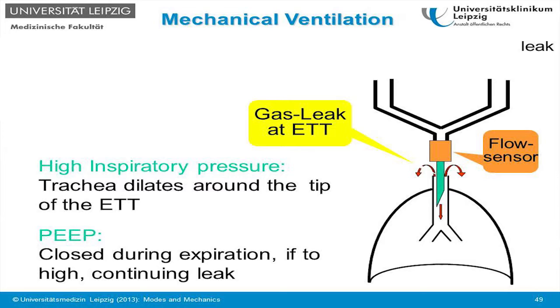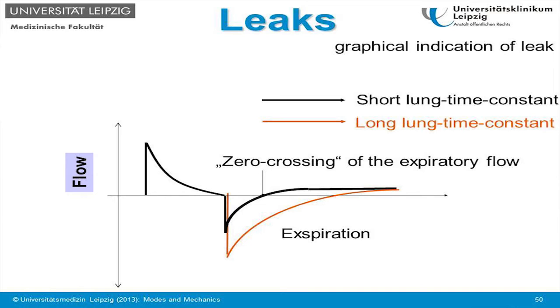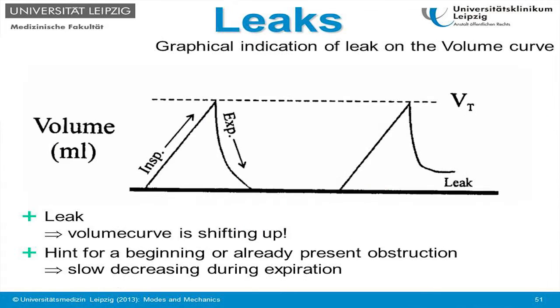So what you also can find out with the flow sensor is leaks. Leaks are especially during inspiration. The trachea dilates and the air will flow out on either side of the endotracheal tube. And you see the leak in the flow curve by a zero line, which is above the actual zero line, and this is the leak flow during expiration. In the volume curve, if you have the volume curve on your screen, then you see the leak by a staircase effect.